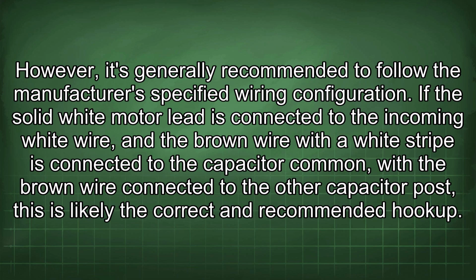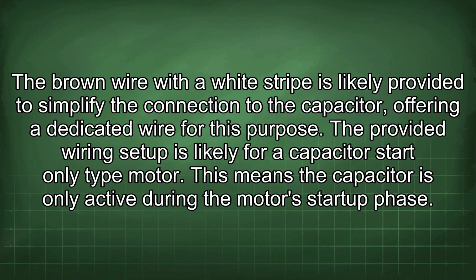If the solid white motor lead is connected to the incoming white wire, and the brown wire with a white stripe is connected to the capacitor common with the brown wire connected to the other capacitor post, this is likely the correct and recommended hookup. The brown wire with a white stripe is likely provided to simplify the connection to the capacitor, offering a dedicated wire for this purpose. The provided wiring setup is likely for a capacitor start-only type motor.